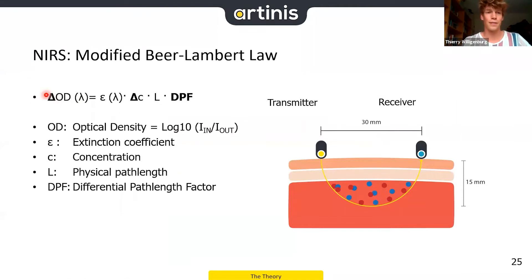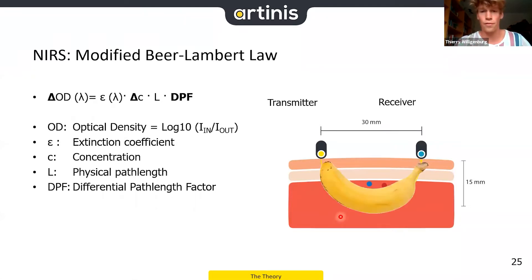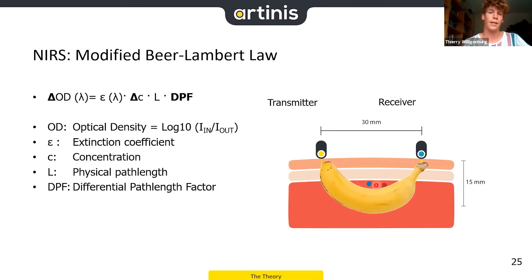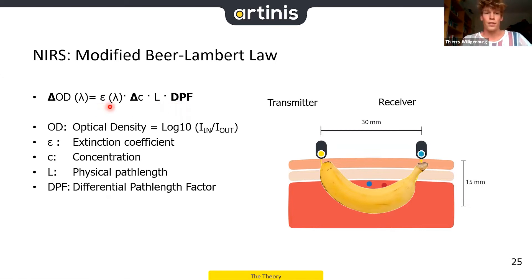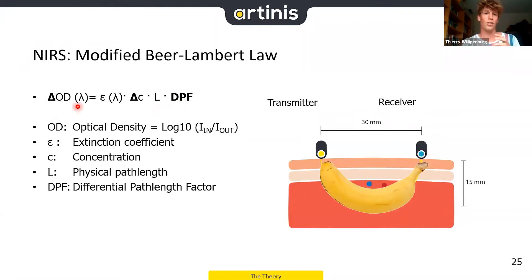In NIRS, we use a slightly adapted version: the modified Beer-Lambert law. We included a delta to measure changes, and we included the DPF — the differential path length factor. In theory, the light path from transmitter to receiver is a thin line, but in practice it's more of a banana shape due to scattering. The DPF corrects for these light losses due to scattering, and is typically set to 4 for muscle research. Since the molecular extinction coefficient, length, and DPF are all constants, a change in optical density equals a change in concentration.